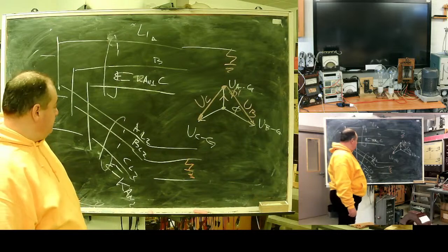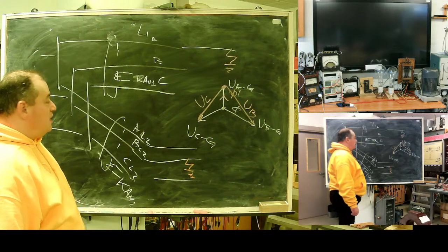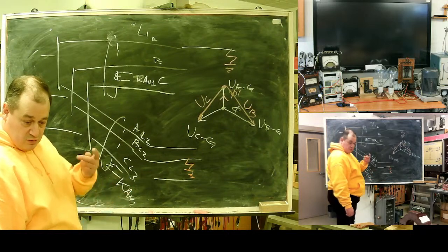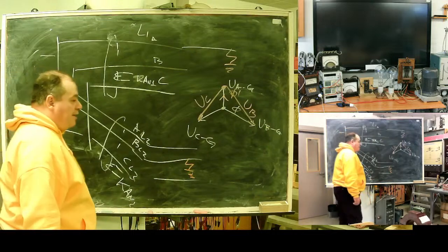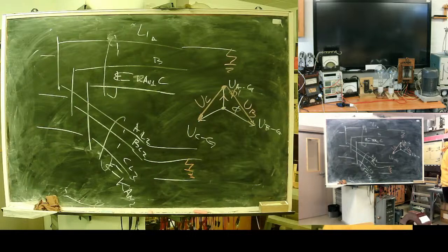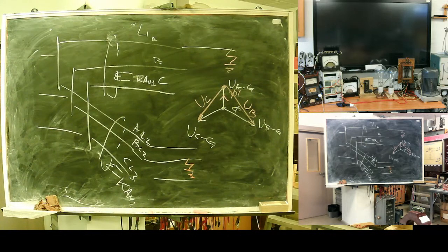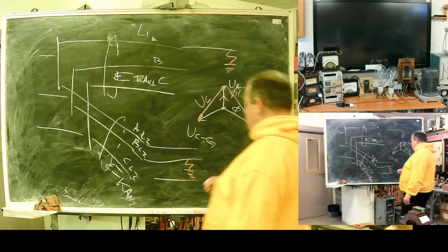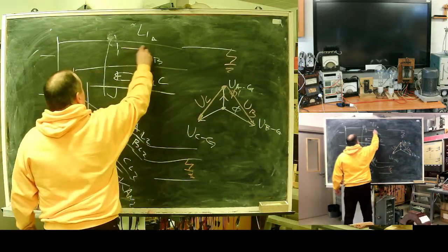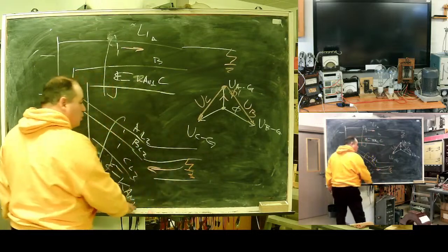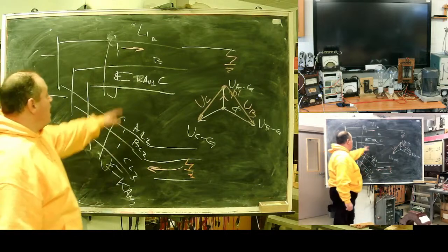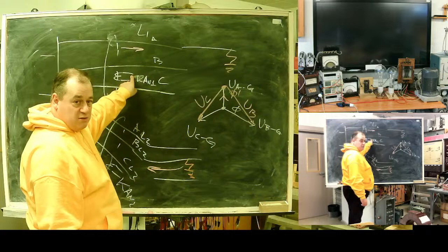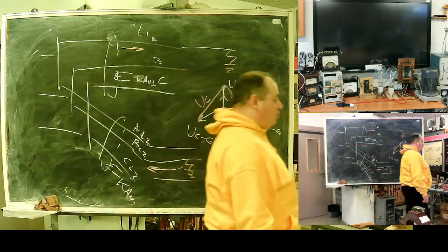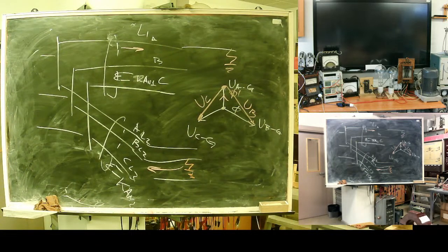Double ground fault. In reality, it's what it now? Line to line AB fault. If Earth fault was, I don't know, 15 amps, this one will be 2,000, 5,000, 7,000 amps. You see real current of the true line-to-line fault. Current here will be not milliamps, it will be dozens of amps. Problem of double earth. Double earth fault is actually a line-to-line fault with a high current.